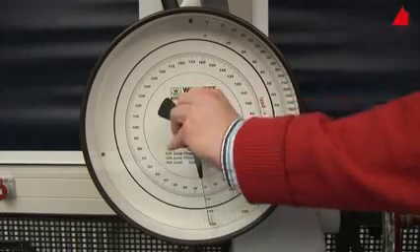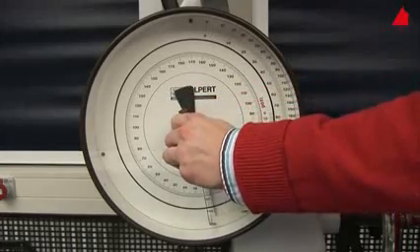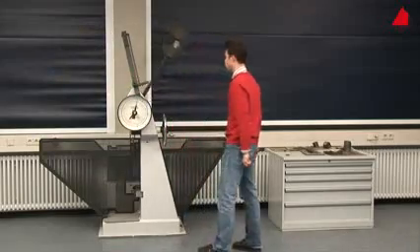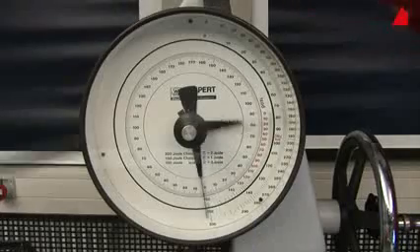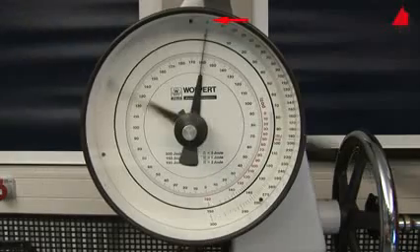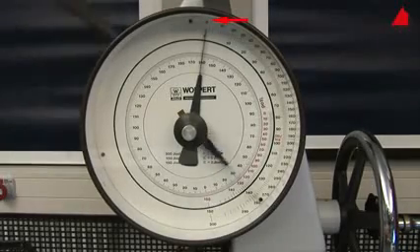In order to do this, he turns the drag indicator downwards and releases the pendulum without a test specimen. The drag indicator stops at position zero. This proves that the pendulum has the correct starting position and that the friction is correctly compensated.